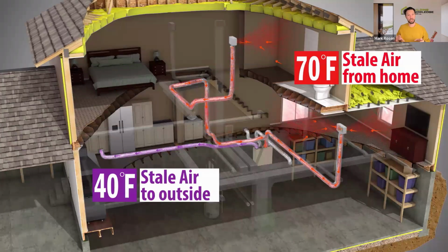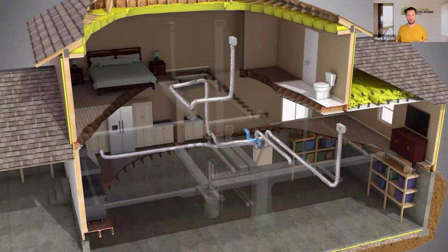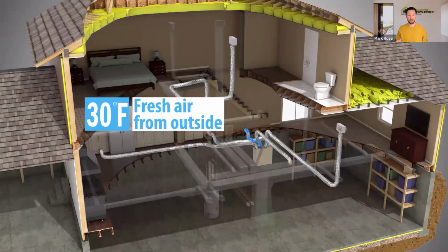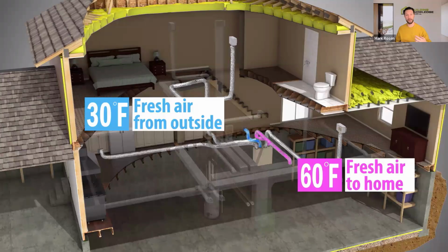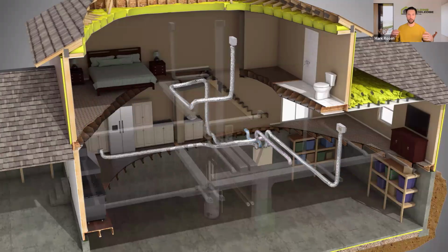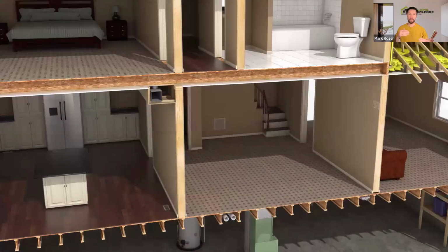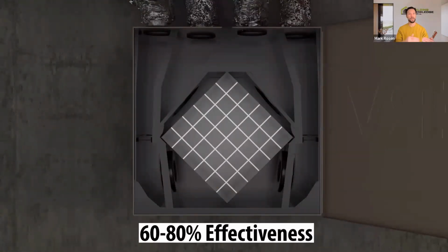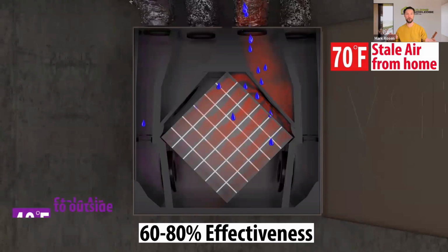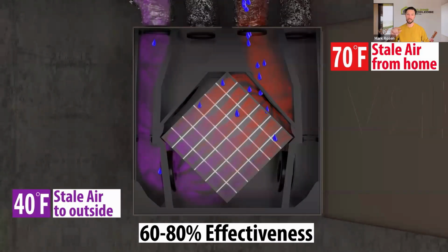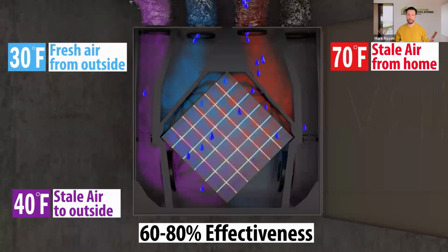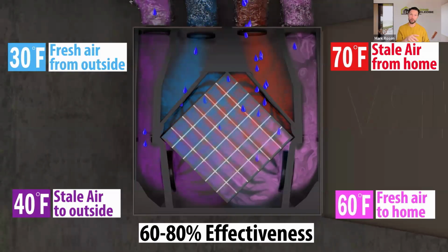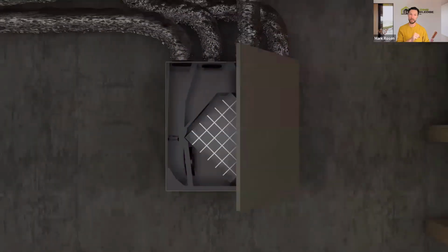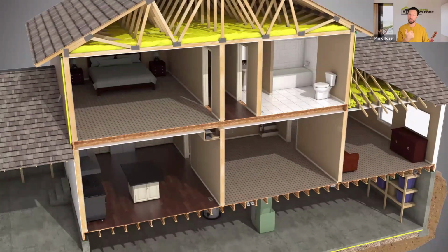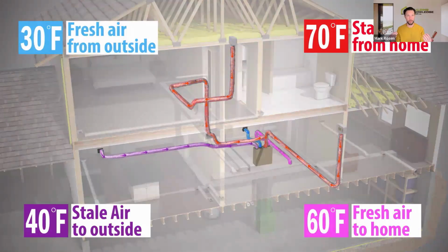The red air is the air being extracted, the stale air being extracted from the various rooms in the home, coming into the ERV. And at the same time, fresh air being pulled in from outside at a much colder temperature is being crossed through that heat recovery core. And you can see the step up there, that 30 degrees Fahrenheit outdoor air was being bumped up to 60 degrees Fahrenheit air before it even reached the furnace. And so the step up that the furnace has to deal with is much smaller in that respect. You also see here that some of the moisture from that outgoing air is being captured and put back into the supply side, which means less load on our humidifiers or dehumidifiers, and overall a more stable interior environment from a relative humidity perspective.